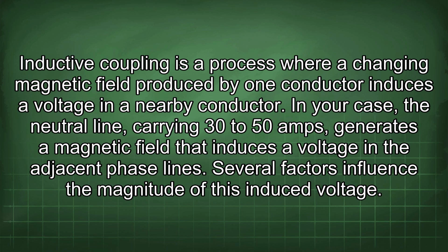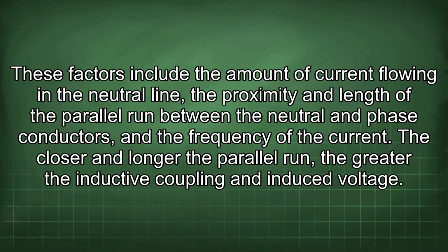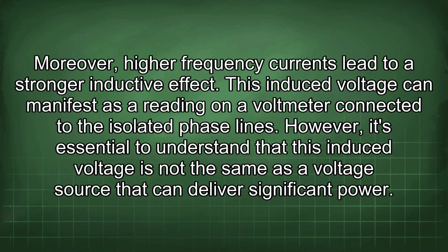Several factors influence the magnitude of this induced voltage. These factors include the amount of current flowing in the neutral line, the proximity and length of the parallel run between the neutral and phase conductors, and the frequency of the current. The closer and longer the parallel run, the greater the inductive coupling and induced voltage. Moreover, higher frequency currents lead to a stronger inductive effect.